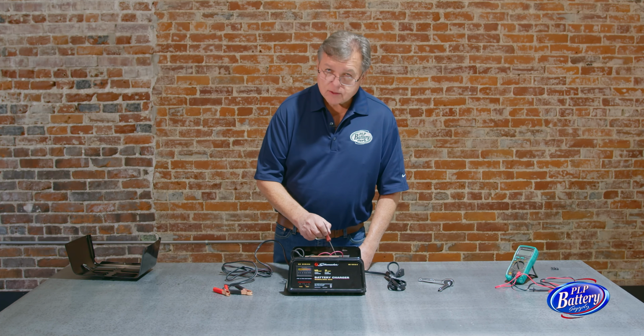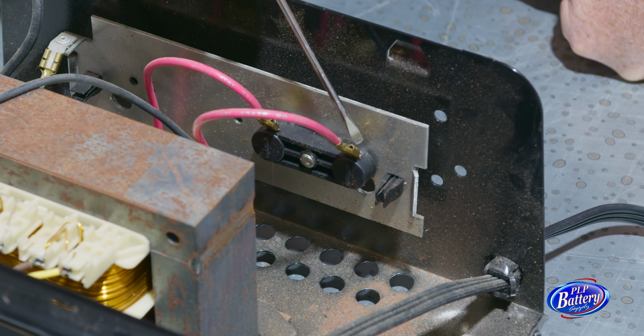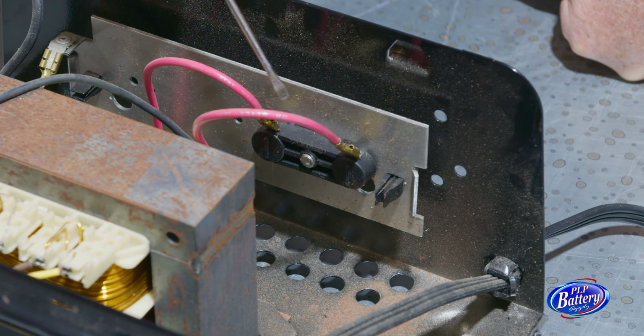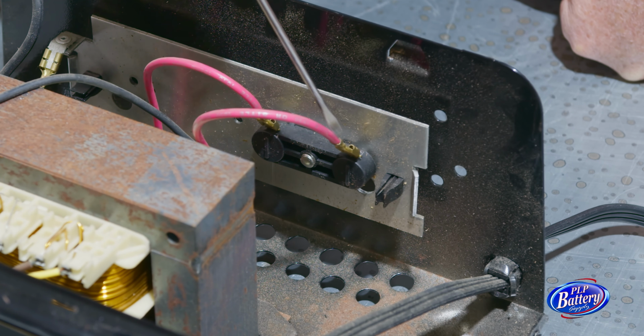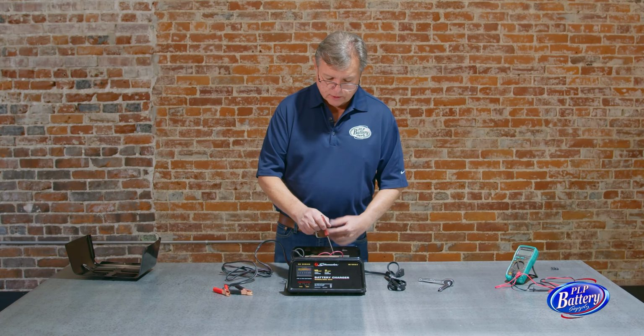9 times out of 10, the failure point is the rectifier, the diodes. In this case it's got 2 button diodes. If I were guessing, I'd say those are probably 25 amp diodes, and they're going to fail somehow.